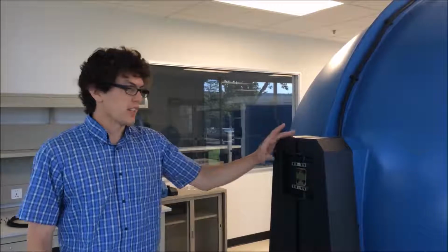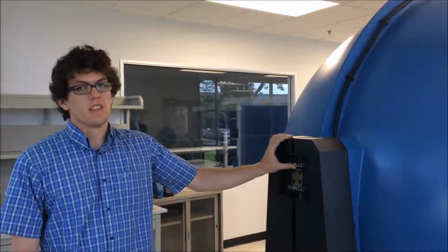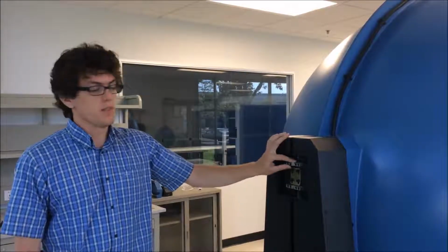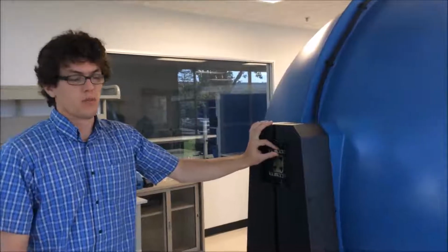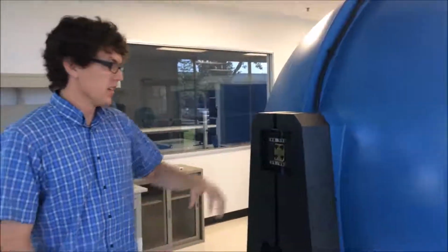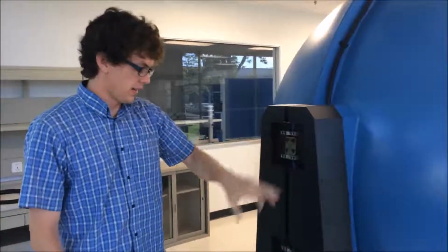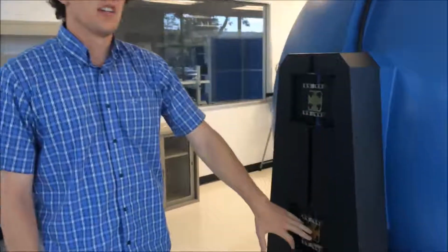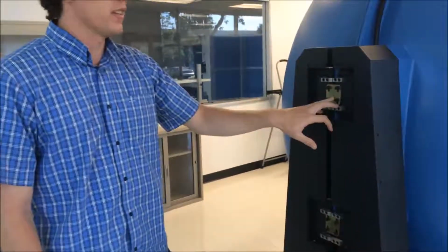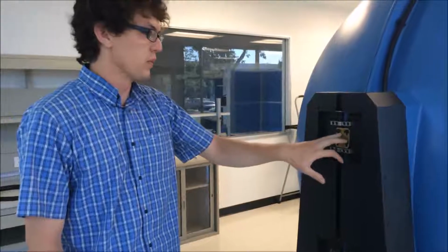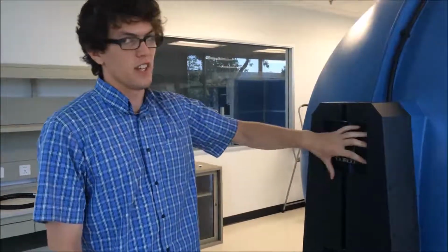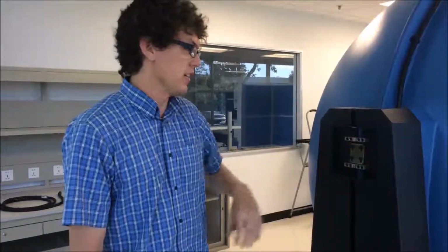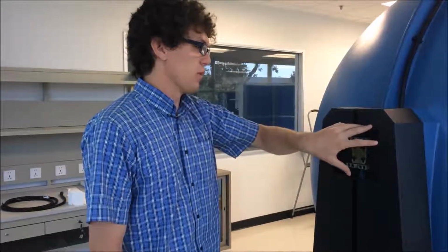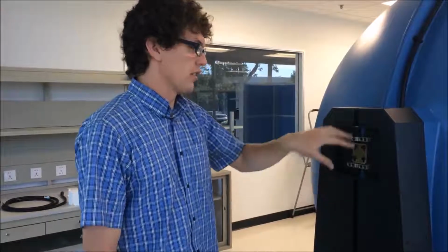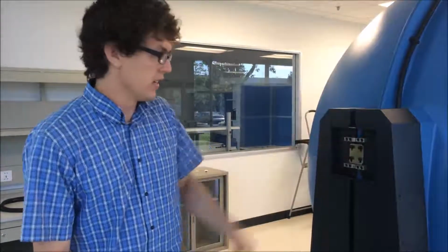Okay, so we finished the cabinet. Now we need to install the sphere system, or at least prepare it for measurement. So when you receive it, you will notice that on the back here, we have these metal plates. These prevent the sphere from opening during shipping. So we need to remove the plates and put on the hinges instead so that we can open it from the other side. You might notice that there will be black plates over the top of here that you have to remove and that we will replace once the hinges are there.